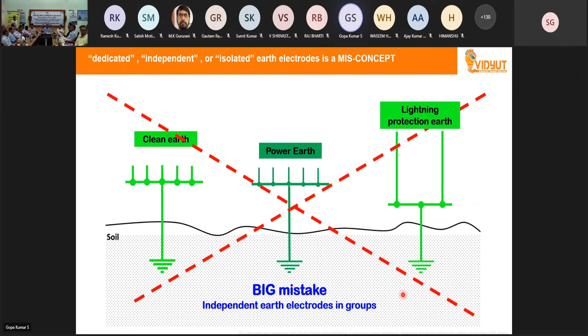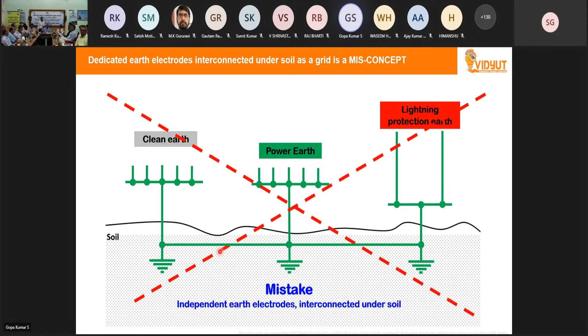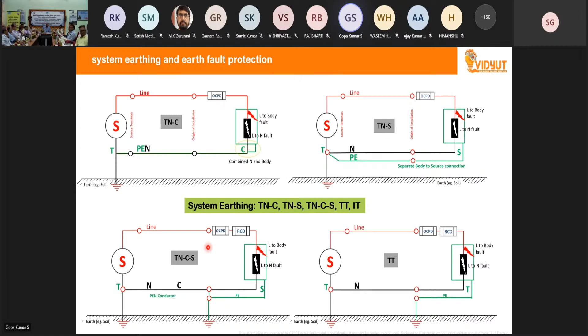It can create a bigger problem. The third big mistake is separate electrical installations with separate earth electrodes in soil, and then interconnecting everything under the soil. In low voltage, of course, this won't work. This is also a mistake. For an electrical installation, one of the first points of safety is system earthing, called TN-C, TN-S, TN-C-S, TT, and IT. You have to find out what kind of system earthing you are making, and accordingly you should follow the system earthing.